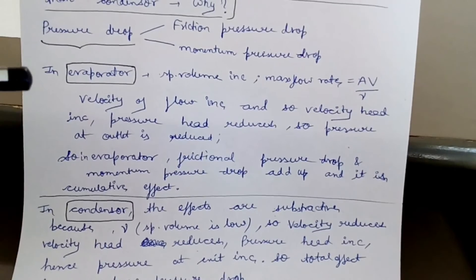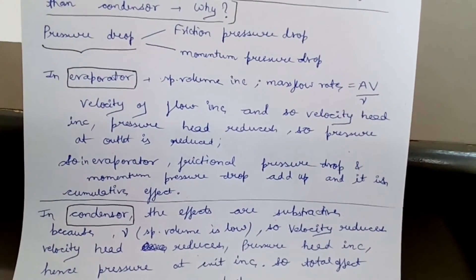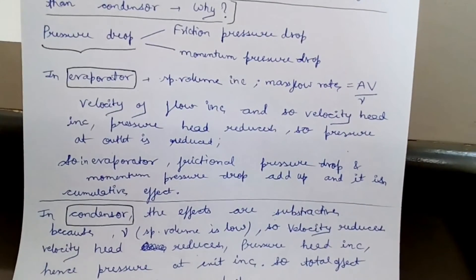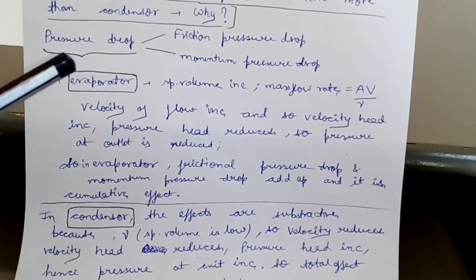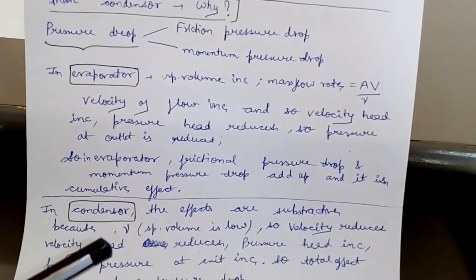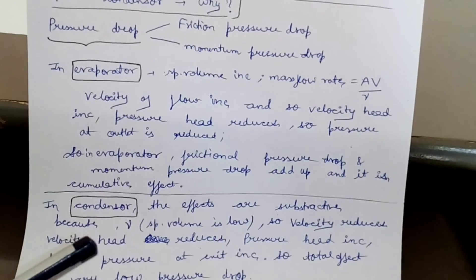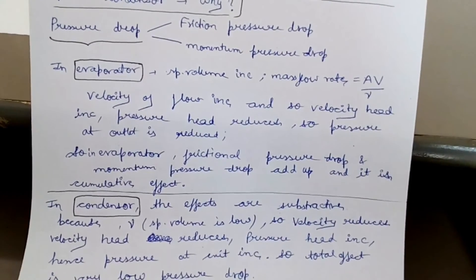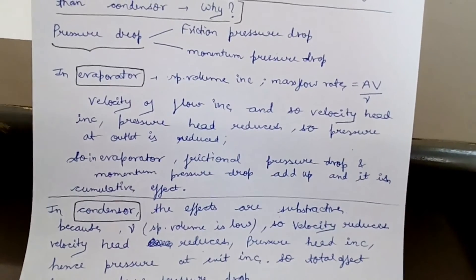In summary: in the evaporator, friction and momentum pressure drops are both negative so there is a cumulative, additive effect and the pressure drop is much more significant. In the condenser, friction pressure drop is negative but momentum pressure drop is positive, so the net pressure drop is low.